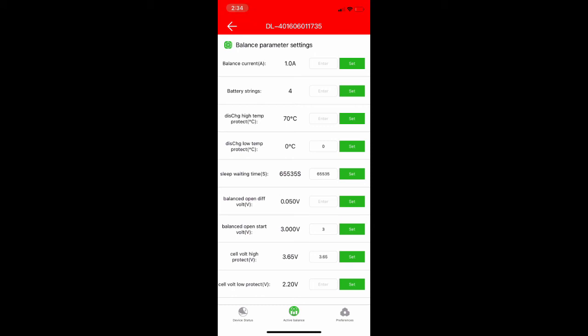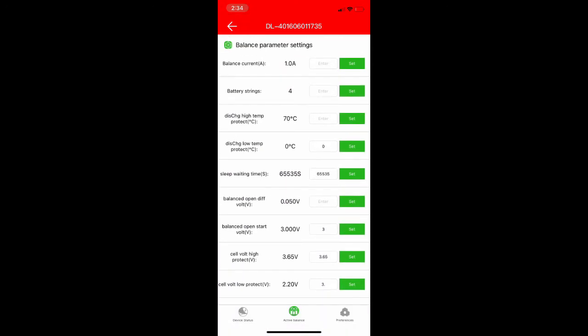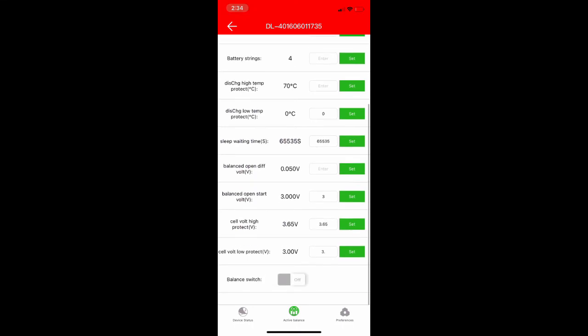And the cell volt low protect is currently 2.2. You could leave it at that, or change it to 3, which is what I'll do - even 2.5 might be a good setting, but I'll leave it at 3 because that's what my low voltage is set to on my BMS. So we'll hit set.